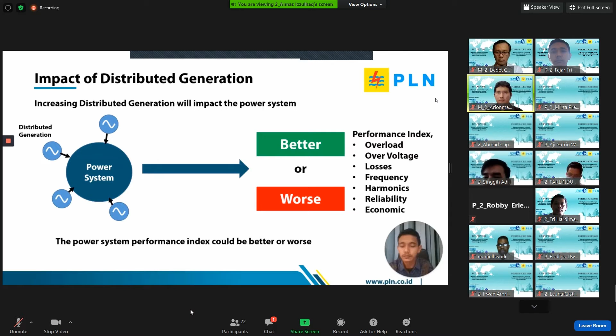Next, I will describe the hosting capacity approach. Hosting capacity can be approached by observing the performance index of the power system. There are three states of performance index. By adding or decreasing the generation, the performance index will go to an improvement state, or the deterioration state, or the acceptable deterioration state. To know how much generation can be connected, it's important to define an appropriate performance indicator. The hosting capacity is based on this. In this paper, active power is selected as the performance index.